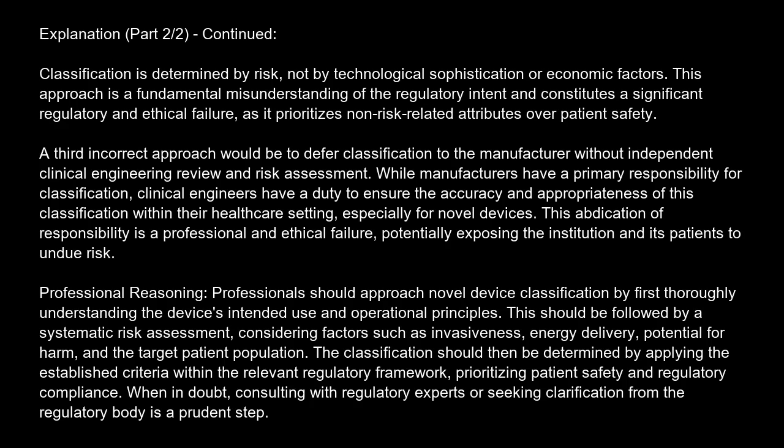A third incorrect approach would be to defer classification to the manufacturer without independent clinical engineering review and risk assessment. While manufacturers have a primary responsibility for classification, clinical engineers have a duty to ensure the accuracy and appropriateness of this classification within their healthcare setting, especially for novel devices. This abdication of responsibility is a professional and ethical failure, potentially exposing the institution and its patients to undue risk.